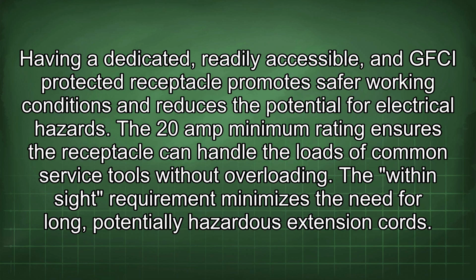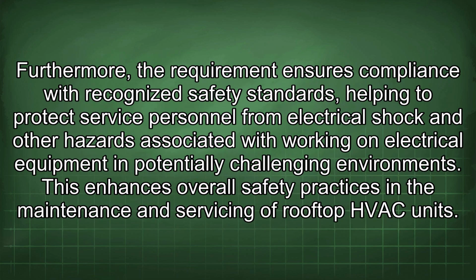The 20-amp minimum rating ensures the receptacle can handle the loads of common service tools without overloading. The within-sight requirement minimizes the need for long, potentially hazardous extension cords. Furthermore, the requirement ensures compliance with recognized safety standards, helping to protect service personnel from electrical shock and other hazards associated with working on electrical equipment in potentially challenging environments. This enhances overall safety practices in the maintenance and servicing of rooftop HVAC units.